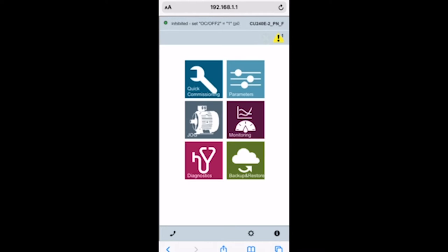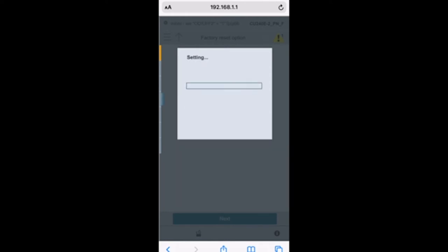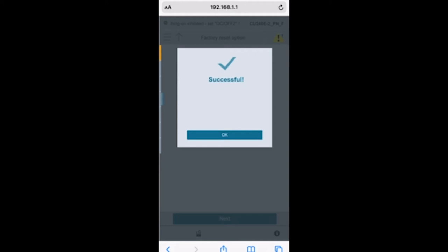Here I've got quick commissioning where I can actually use my motor nameplate data and go through and commission the drive. I'm going to go ahead and do that. Let's reset the factory settings right here. While that's doing that, you want to make sure you've got your nameplate information from your motor. I've got mine, it's a little one horsepower motor.